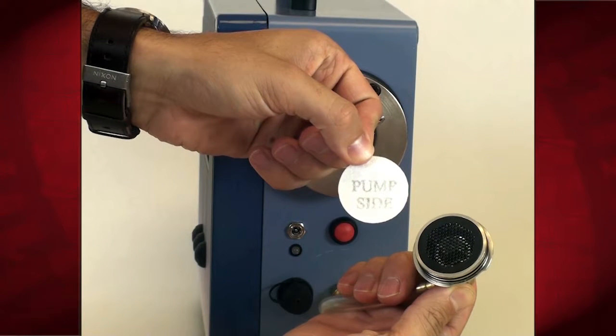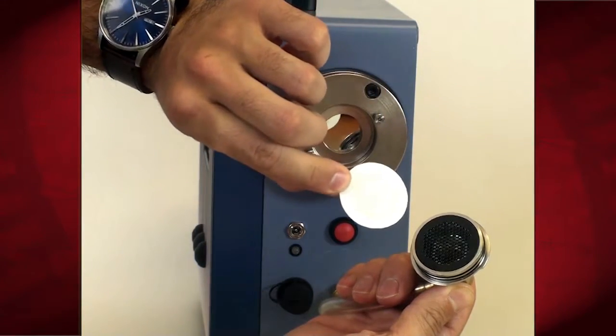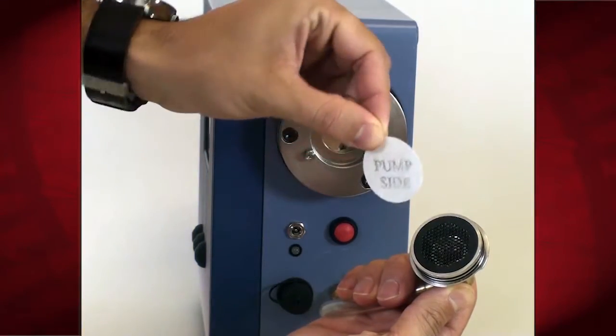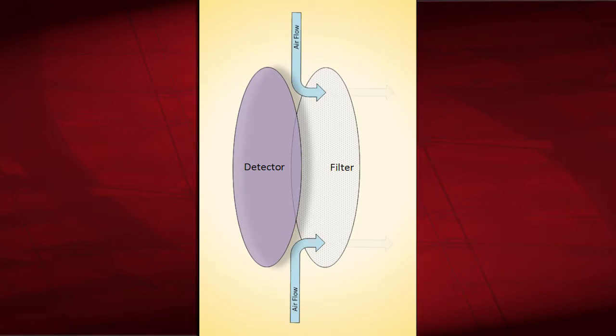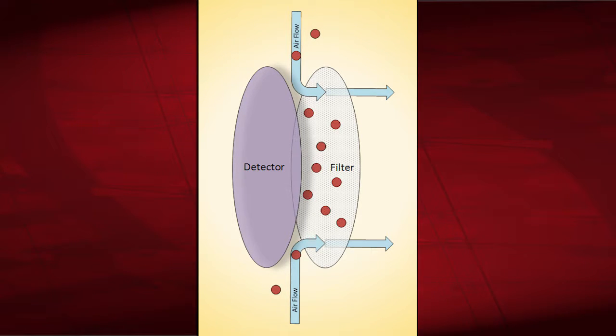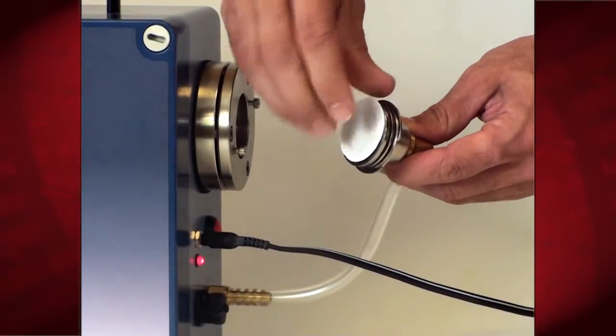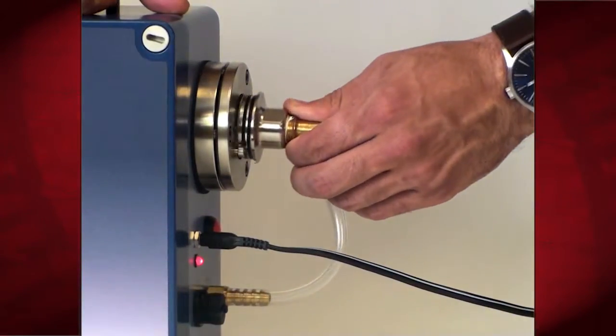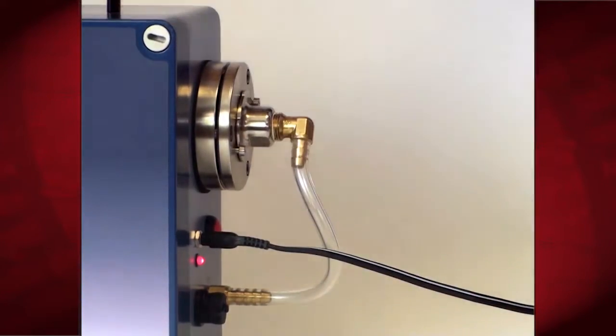You will see the words pump side. This is the correct direction to install a filter. With the smooth face towards the detector and the shiny fibrous side reading pump side against the black filter support. Measurements are made by pulling air through this filter, depositing particulates on its surface which are constantly monitored by the detector. When the captured particulates decay, the emitted alpha and or beta particles are detected by the BPM. Ultimately, this is what allows the instrument to measure and alarm on radioactive particles. Now, just realign the filter correctly, push the filter holder back in, and twist it to lock under the screws.